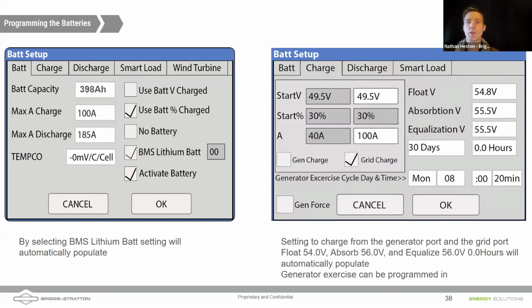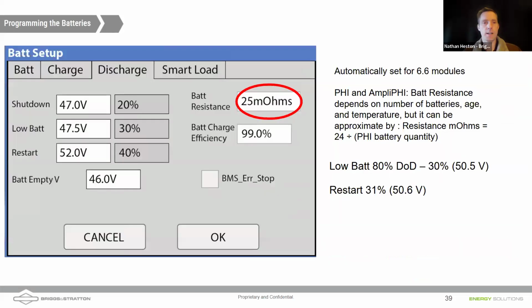Absolutely. So that absorption voltage is when you exit the bulk phase, which is the constant current part of the charge cycle, and you go into the absorb phase, the constant voltage part. And then float, if you do have a renewable source like solar, it'll just keep those batteries topped off at 54 volts. So you can program that in. That's below on the bottom right-hand side of that slide there. And like we said earlier, everybody's going to get a copy of this slide deck. So let's go ahead and go to the next slide.